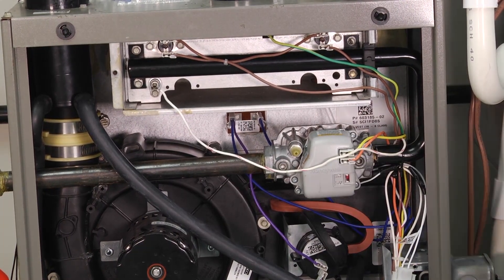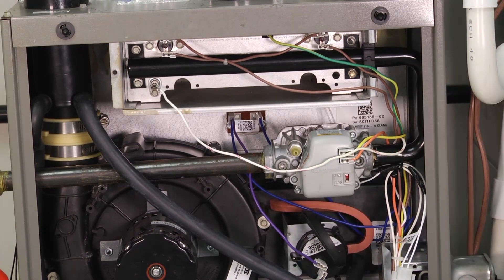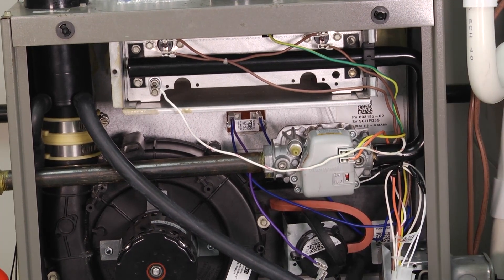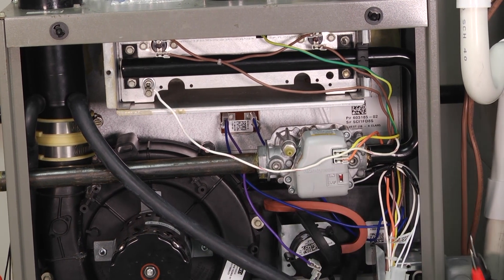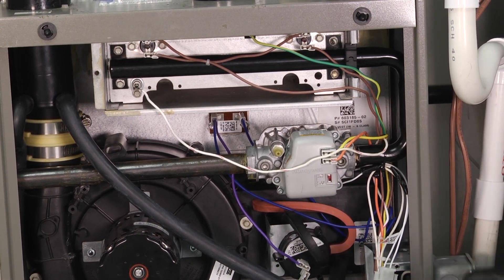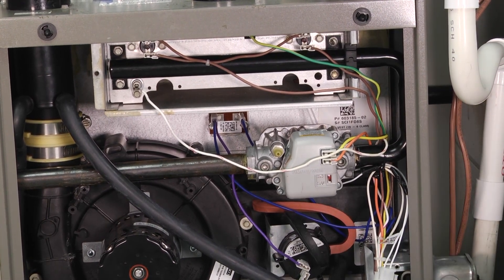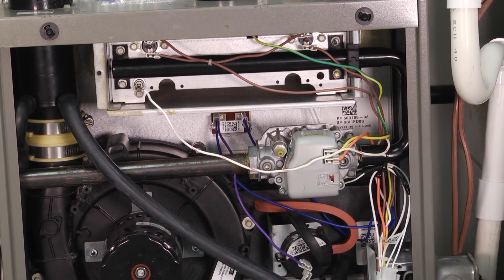Some of them may say between 13 and 19 ohms, we consider that good. And you can have some really high between 150 to 200 ohms would be considered good. But definitely check with documented information to figure out what the range that that particular igniter that you have in your system needs to be at when you check it.